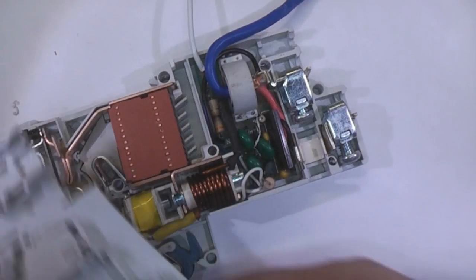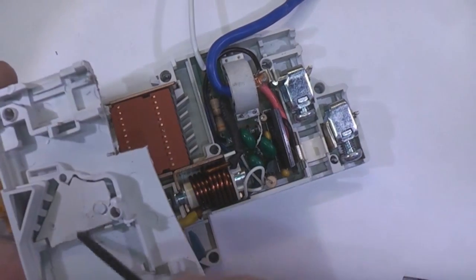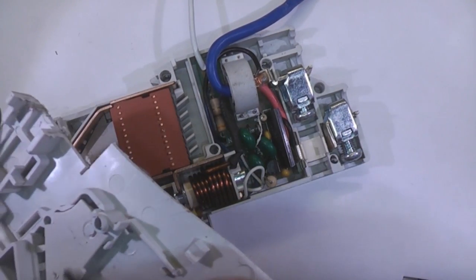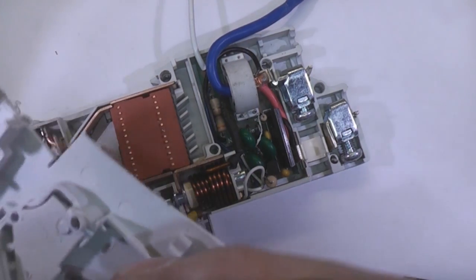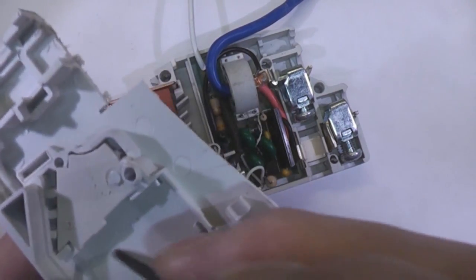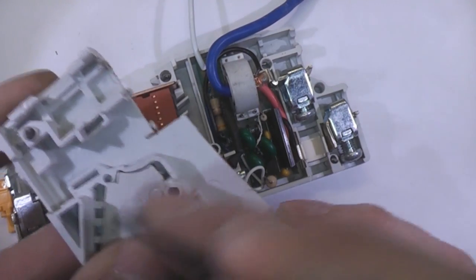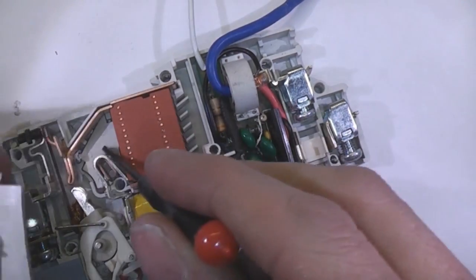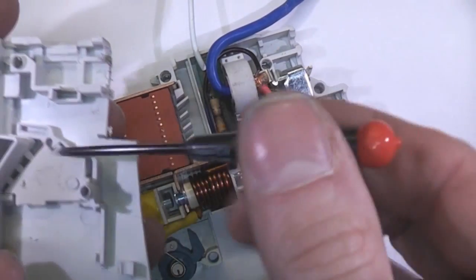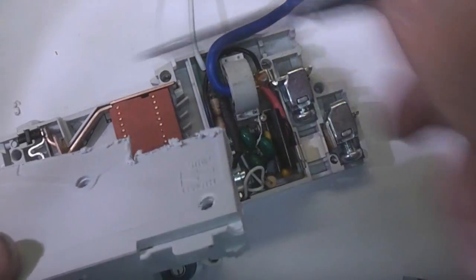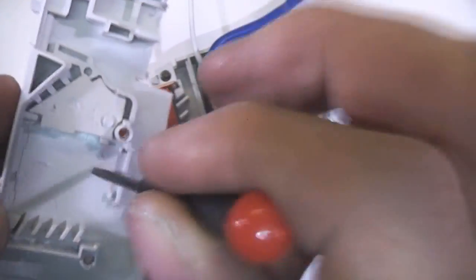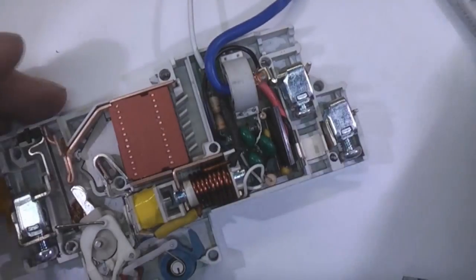The other thing that you see on here, both in here and here, there's these sheets. Now some circuit breakers actually have ceramic, but this actually looks like plastic, but it does look like a different type of plastic to the main case. It feels like it's maybe quite heavily glass filled, so again that's to do with, if you've got an arc here, preventing it basically melting its way through and possibly onto adjacent circuit breakers, or generally out of it. So this is some protection. This does actually feel quite hard. It is a plasticky material, but it feels like a very heavily filled plastic material. You can just hear how it sounds different when you tap it. So that's some additional protection on there.